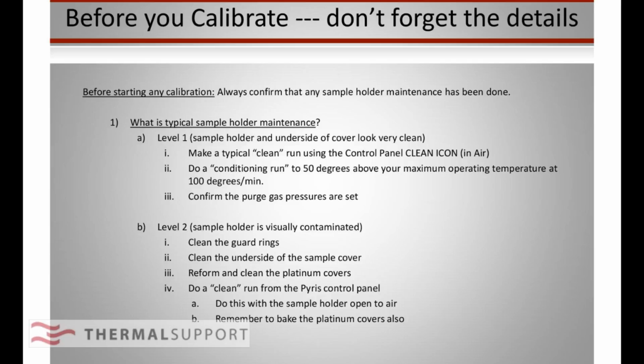Then you're going to do a level 2. It's visually contaminated, you want to clean the guard rings, you need to clean the underside of the sample holder, you need to reform and clean the platinum lids, you need to do a clean run, all that needs to be in air. By the way, if you try to do a heating clean run with a DSC or a TGA or anything else, and you're in a nitrogen environment or anything else, it's not going to work so well. You really need the air or oxygen to really start burning stuff off where you should have it.